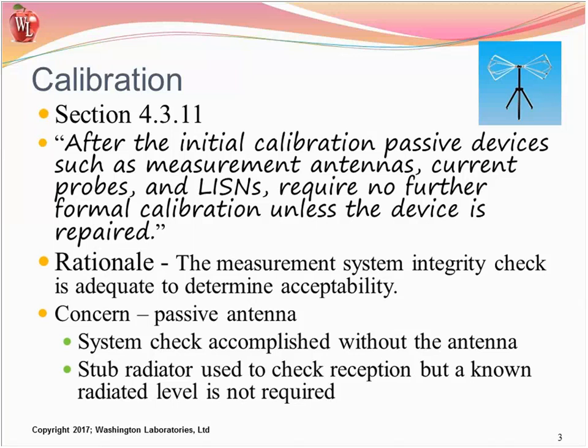It's always been a concern that our antennas are doing the right thing, and it's pretty easy for minor things to creep in without us looking at that. So in looking at the calibration, it's not an automatic pass to get rid of that. For instance, a current probe could have a fracture or an anomaly that doesn't show up at the selected frequency. So we have to be very cautious about what we're doing here and not blindly look at this as being the end-all.